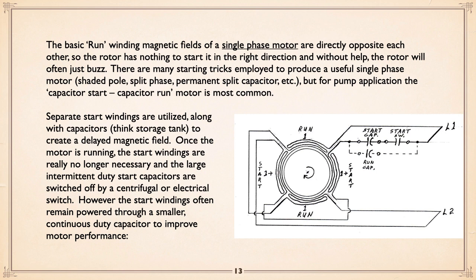Three-phase motor, no problem. It is a rotating field. The problem when you get to single phase is there's nothing to cause it to rotate. In other words, basically you've got windings that are opposed on either side of each other, and it's either one is north and the other is north or whatever, top and bottom. There's nothing to tell the rotor which way to go. Sometimes you get lucky and the magnetic field will give it a bit of a kick and the thing will go one direction or the other. You never quite know which. Or it'll sit there and buzz.